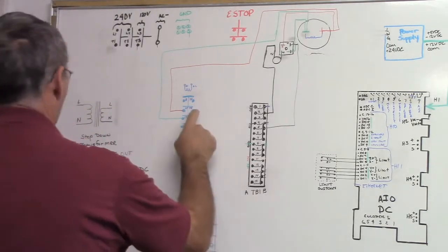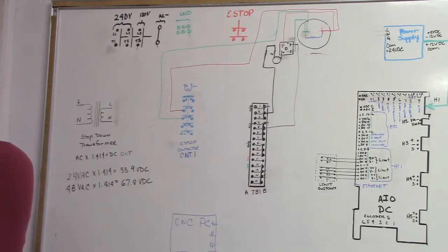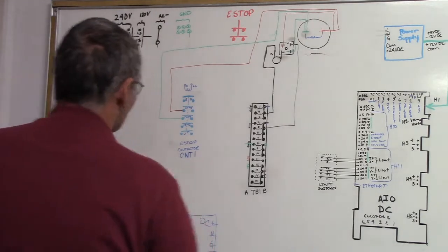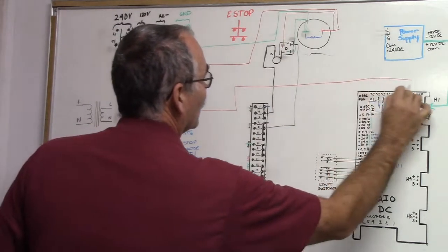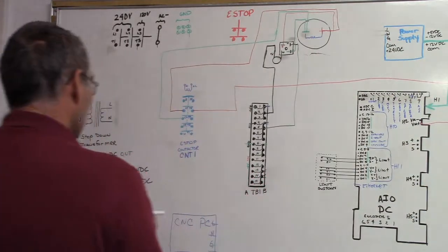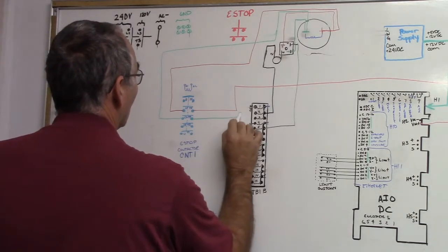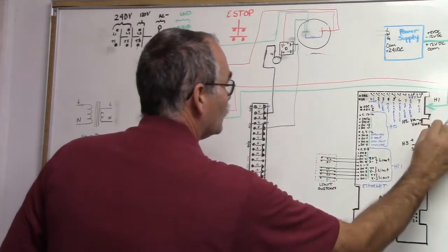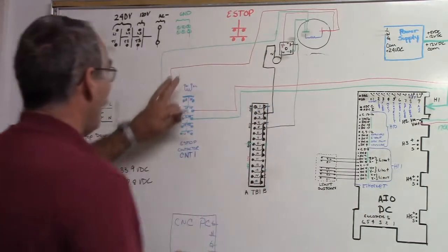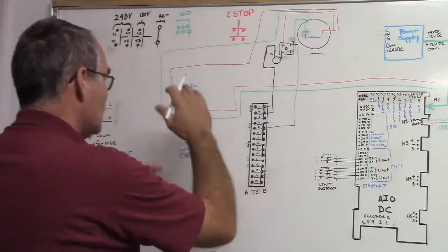I'll backtrack and we'll put the transformer in the circuit and we'll do the same thing there. So now off the backside here, we want to get over to our all-in-one DC. We're going from T4 to plus VM. So T4, we're going to plus VM. And then we're going to CNT1, T3 to our VM minus. So now through this system, we have 170 volts DC here.